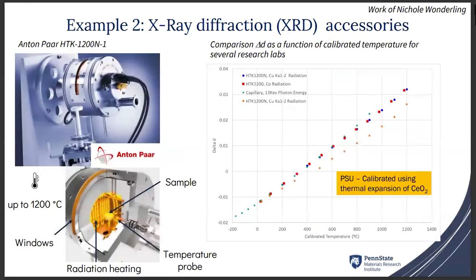Now I will discuss a second problem, which is non-ambient XRD. This work was done by Nicole Wonderling. It was done using this HTK 1200N from Anton Paar that can span the temperature from room temperature up to 1200 degrees Celsius. We put the sample here. We have radiation heating, the temperature probe close to the sample, and the windows around it in order to collect the XRD data.